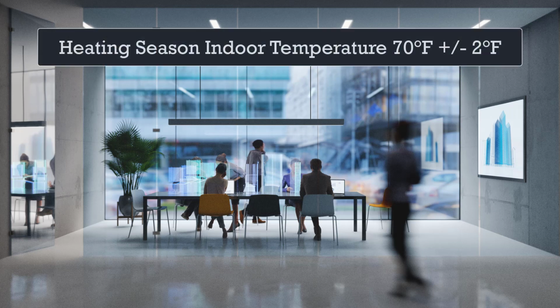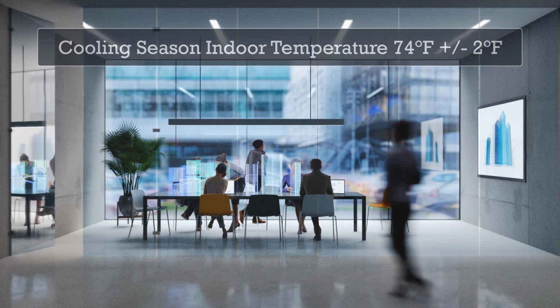With these factors as a background, our Optimum Start simulation will be based on indoor temperature set points of 70 degrees Fahrenheit during heating operation and 74 degrees Fahrenheit during cooling operation.